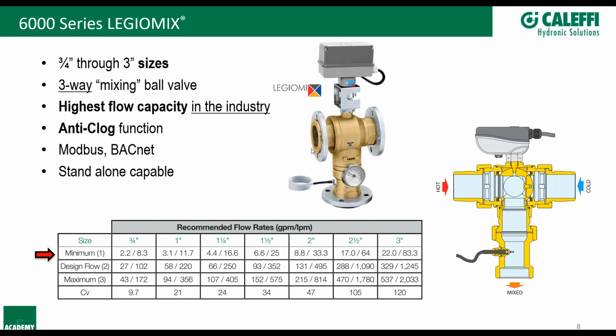Okay, so if you are sizing by pipe size, I can just about guarantee you're going to oversize this mixing valve. And if you do oversize the mixing valve, the one thing you're going to run into is that you're going to pay more, first and foremost, pay for something you don't really need. But then you're also going to have issues with the minimum flow requirements. So if you got a 2-inch pipe size and you're running 50 gallons a minute through there, you don't really need a 2-inch valve. You could really get away with 1.25 inch that has a design flow rate of 66 gallons per minute and just neck down to it. So the idea here is you want to size it based on flow and size it based on pressure drop. And, again, if you do oversize it, you're going to run into minimum flow requirements.